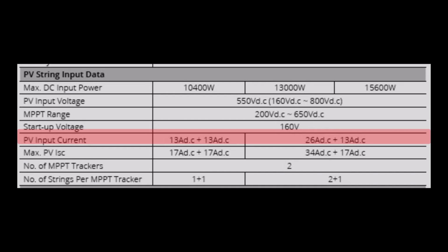The next line, the PV input current, shows you that on the 12 kVA unit, the first MPPT controller can handle 26 amps direct current, and the second MPPT controller can handle 13 amps direct current. The maximum PV ISC is the maximum current if there is a short circuit. The SC stands for short circuit. The first MPPT controller can handle 34 amps DC, and the second one can handle 17 amps DC.